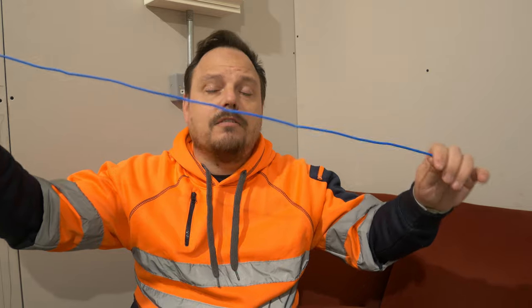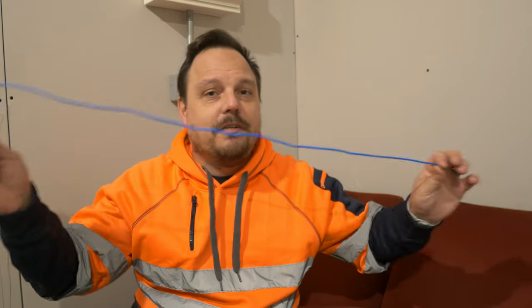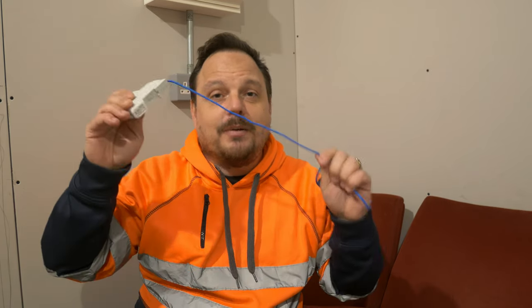So I'm not going to go to that trouble, but you've seen me put them in the board just to show the difference in size. They have a nice long fly lead on, and that can work both ways for installers. I've seen people getting frustrated when they're doing their commercial distribution boards and the fly leads are too short to reach the neutral bar. And equally, I've seen people getting very upset that they have to cut down every single fly lead in a small domestic board just to reach into the neutral terminal bar, or tuck everything behind the DIN rail with loads of unnecessary wire.